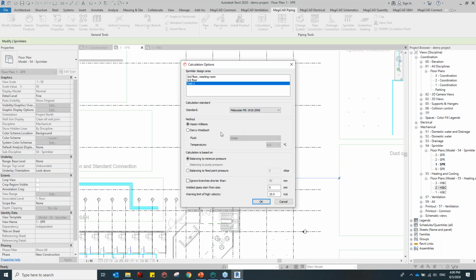For example, let's take the Malaysian standard using the Hazen-Williams formula and balance to the minimum pressure. So there are different options here. Balance to the minimum pressure is nothing but, if you're not connected to a pump, it will calculate the required pressure for us. There is a second option: if you have a pump, you can also connect to the pump and balance to the pump pressure, so that you can understand whether this is workable or not, right? In some cases we have renovation projects where we already know the fixed pressure, so we have to follow that fixed point pressure. Then you can use a fixed feed point pressure, and it will automatically size according to that pressure.